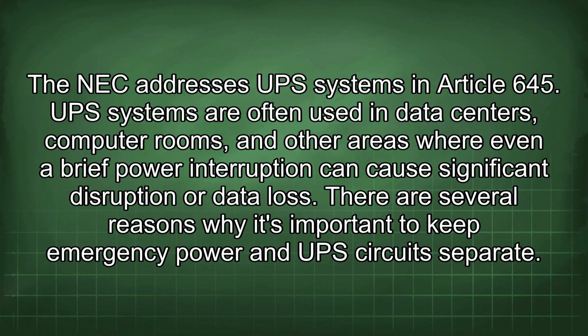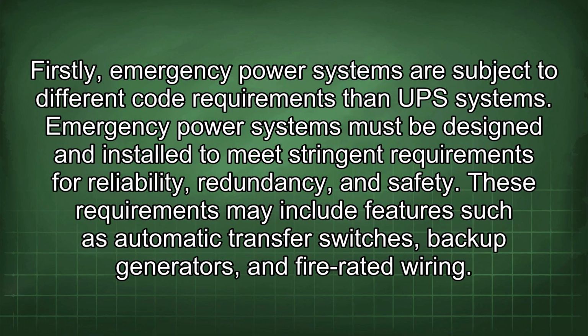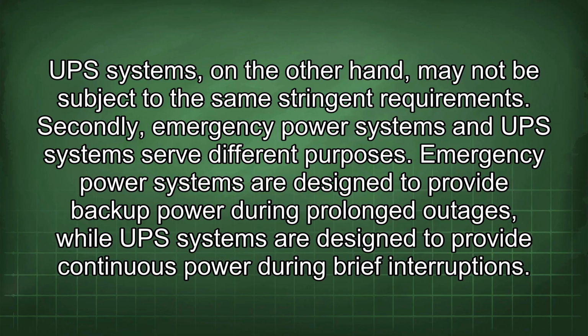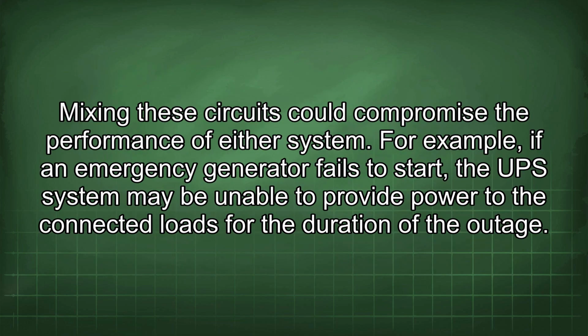There are several reasons why it's important to keep emergency power and UPS circuits separate. Firstly, emergency power systems are subject to different code requirements than UPS systems. Emergency power systems must be designed and installed to meet stringent requirements for reliability, redundancy, and safety. These requirements may include features such as automatic transfer switches, backup generators, and fire-rated wiring. UPS systems, on the other hand, may not be subject to the same stringent requirements. Secondly, emergency power systems and UPS systems serve different purposes. Emergency power systems are designed to provide backup power during prolonged outages, while UPS systems are designed to provide continuous power during brief interruptions. Mixing these circuits could compromise the performance of either system.